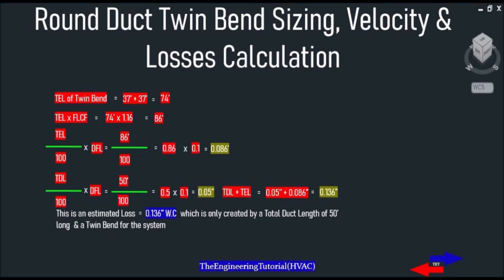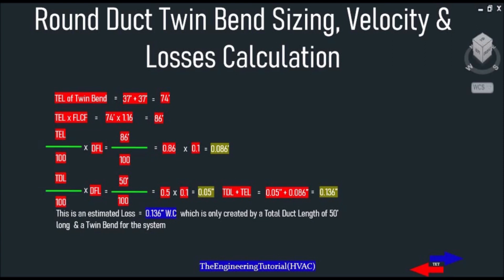So we have a total equivalent length of 37 feet plus 37 feet equals 74 feet. If we multiply the total equivalent length of 74 feet by a fitting loss conversion factor of 1.16, we get a corrected total equivalent length of 86 feet for our round twin bend. Then if we divide the total equivalent length of 86 feet by 100 and multiply by a design friction loss of 0.1, we get a loss of 0.086 inch of water column.